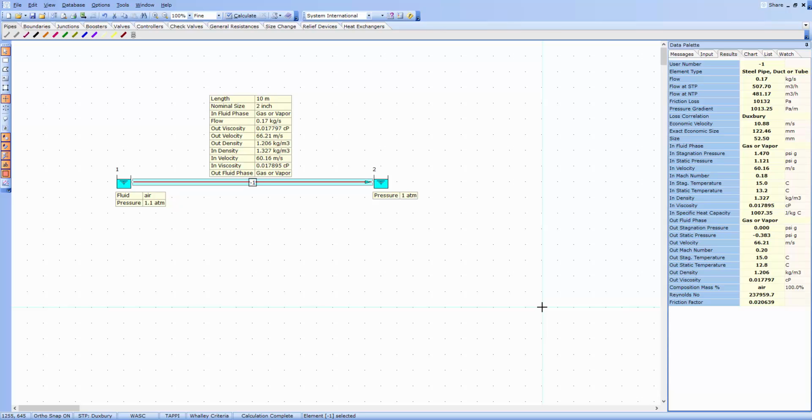And applying real gas flow conditions, of course, gives us a much higher degree of accuracy, particularly for high pressure, high flow rates, low temperatures, or the closer the gas is to change in fluid phase state. Under these circumstances, if gas ideality has been assumed, the level of error in calculation can be significant. In systems with multiple branch pipe connections and multiple fittings, the design and calculation of gas flow systems becomes quite complex, and assuming gas ideality compounds the magnitude of error in the final solution. But the main thing to note here is that fluid flow software doesn't make this simplifying assumption.